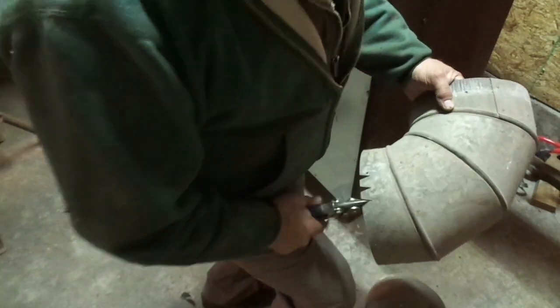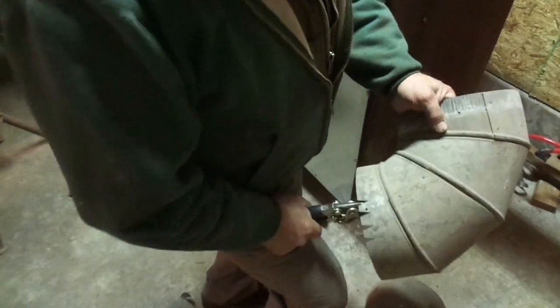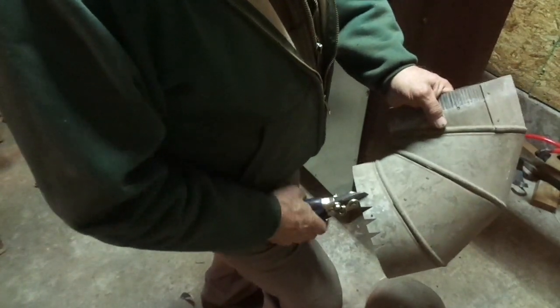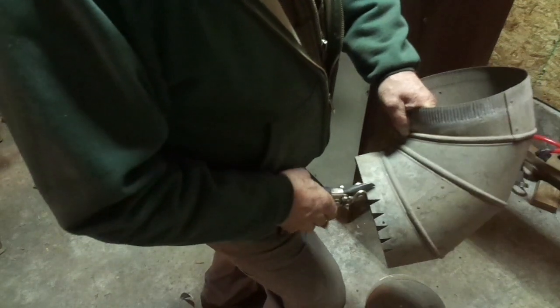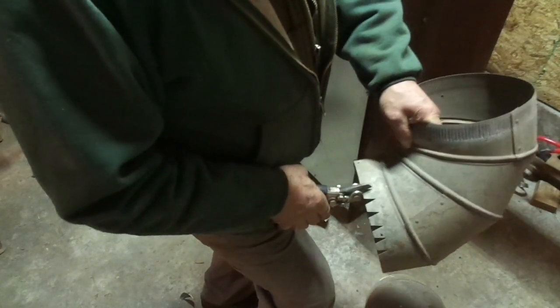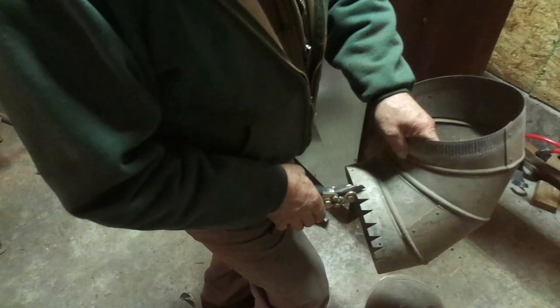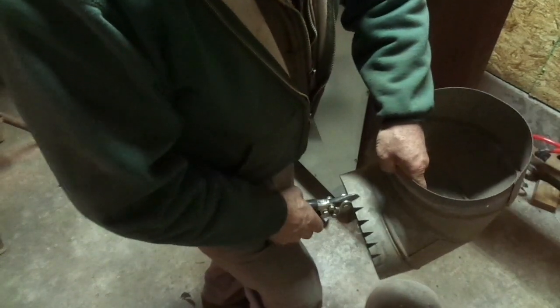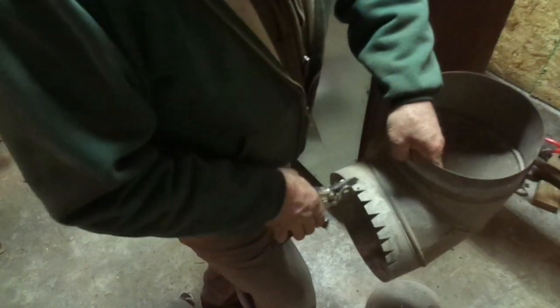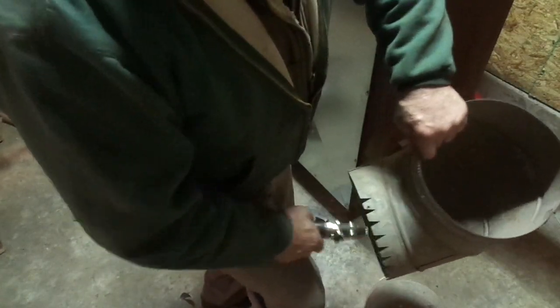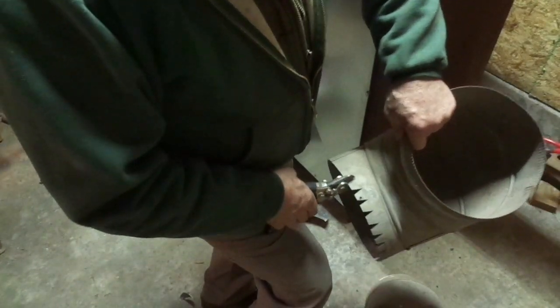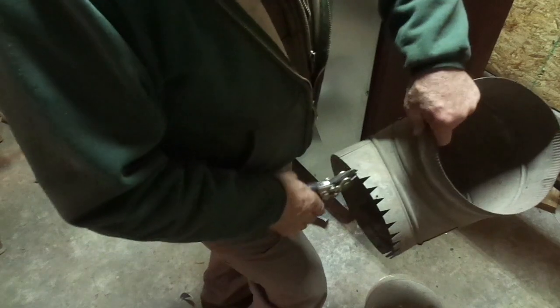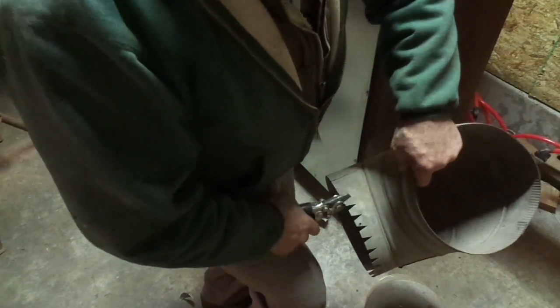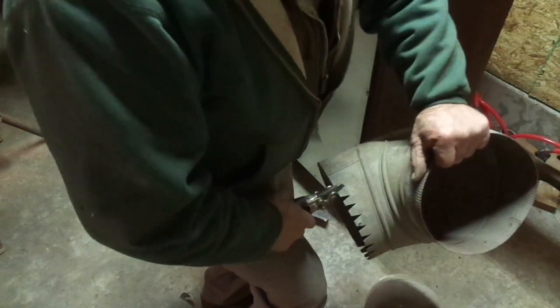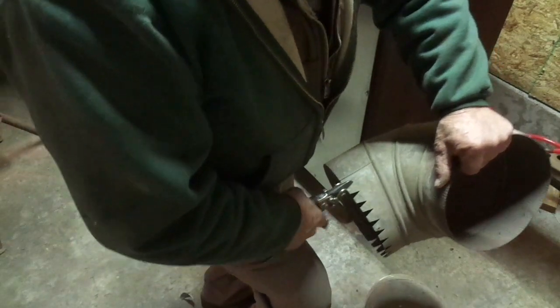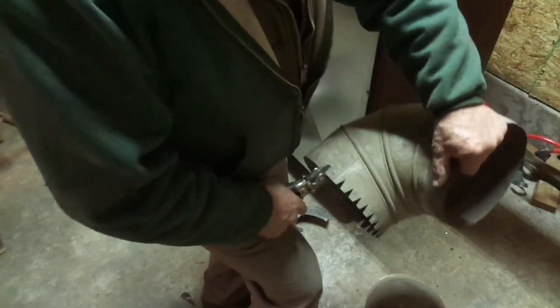Bear in mind, you're going to be bending these tabs over with your fingers, so the thicker the material on the fitting, the smaller you want those 30-degree V-notches. This here is a pretty tough material, and my fingers are going to get tired by the time I get them all bent over. We're going to take a select few and bend them to the outside so that the fitting will not fall down inside the plenum opening, and then we'll stick the rest of them down inside.